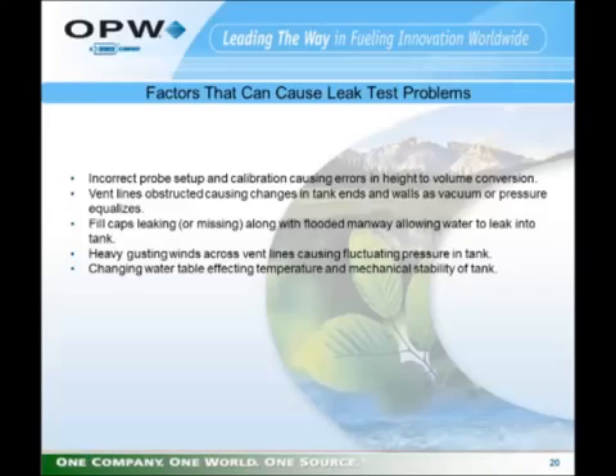One thing not mentioned here that can also cause problems with the leak test is if you have a tank that is not used very often. The product in that tank tends to layer out in different temperatures, and because we have different temperature levels in the tank, that will also affect tank testing and will usually give you an inconclusive test result.